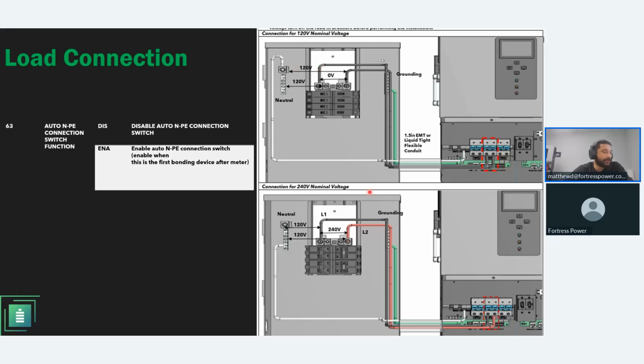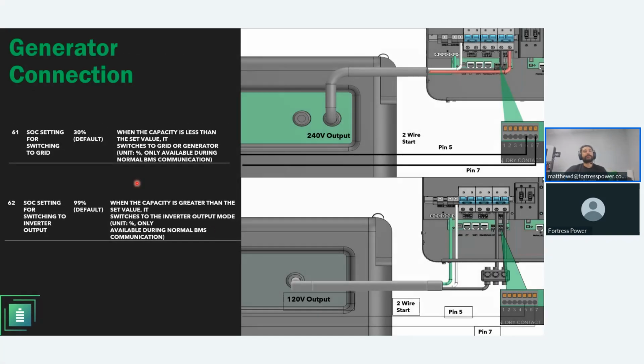In a standard typical residential application, you would do 240 volt single split phase, and you would really do that if your property is using 2 pole devices, as I mentioned before. So here we can see single pole breakers. Here we see 2 pole breakers, right? For typical electric devices. Then you have your generator connection.